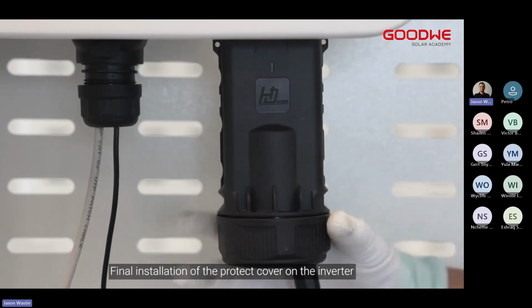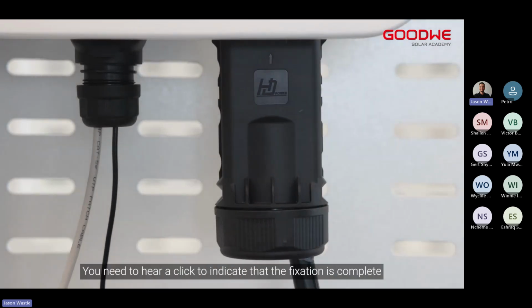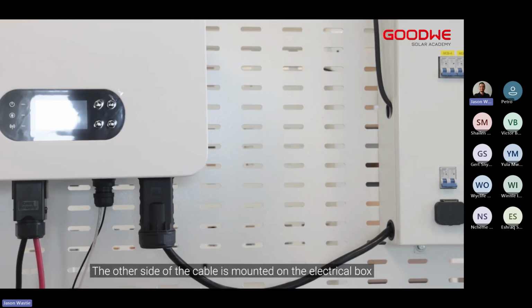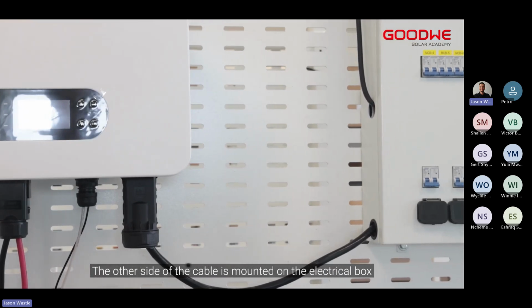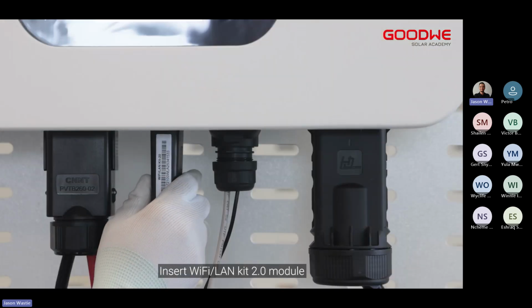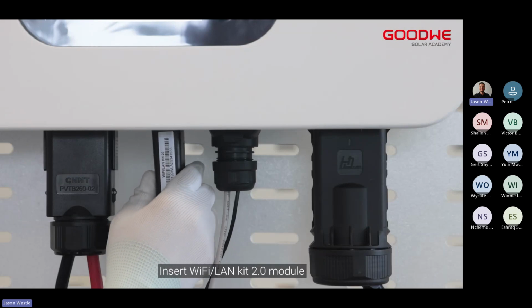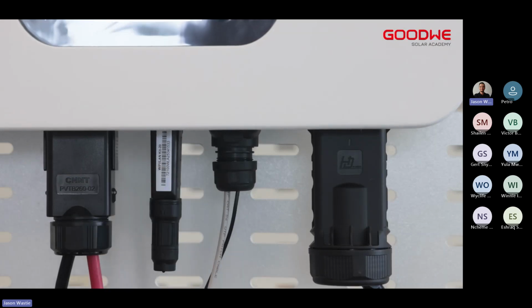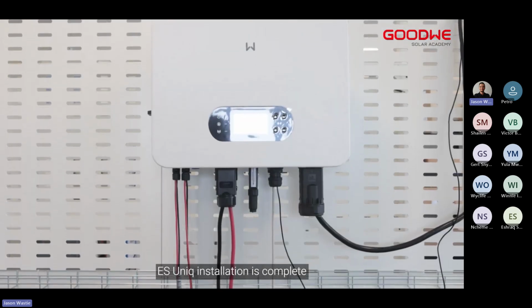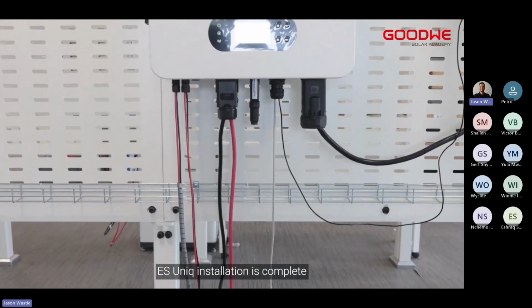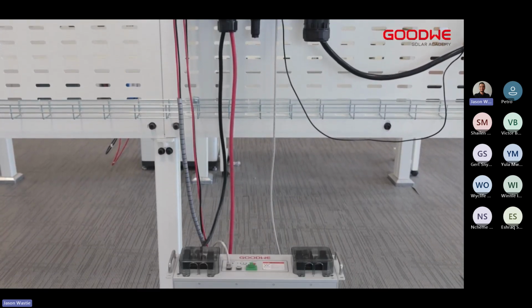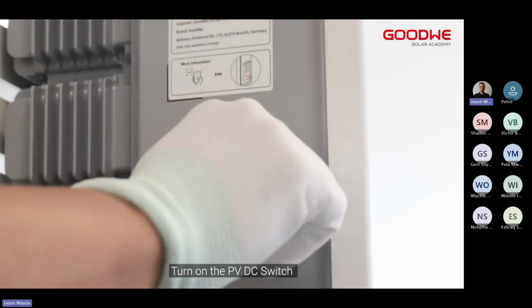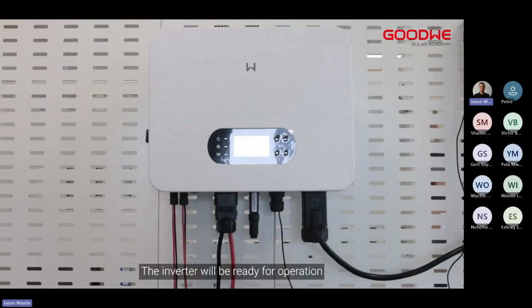Final installation of the protect cover on the inverter. You need to hear a click to indicate that the fixation is complete. The other side of the cable is mounted on the electrical box. Insert Wi-Fi/LAN kit 2.0 module. ES Uniq installation is complete. Turn on the PV DC switch. The inverter will be ready for operation.